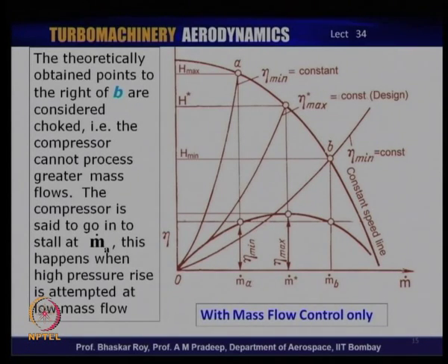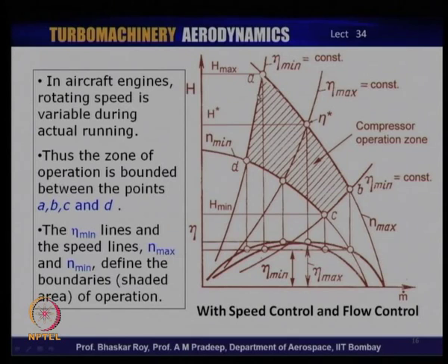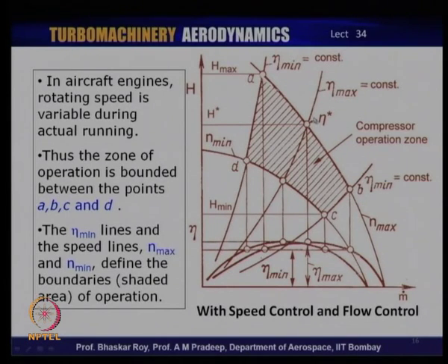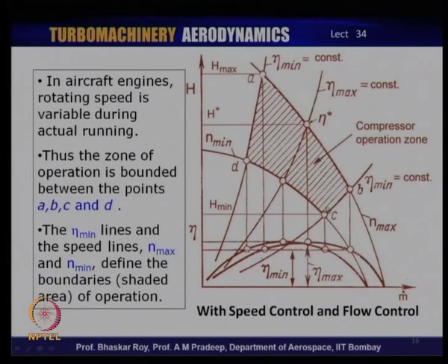However, if you have mode controls — speed control and flow control together — you have a zone of operation bounded by two speed lines: the maximum speed line N_max and a minimum speed line N_min, and a minimum efficiency line η_min. In this bounded shaded region A–B–C–D, the entire centrifugal flow operation can take place. So from a single-line operation from A to B, the centrifugal compressor can now be operated over the entire zone ABCD — enabled by having independent speed control and mass flow control.